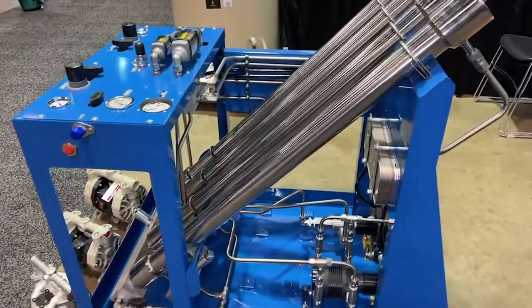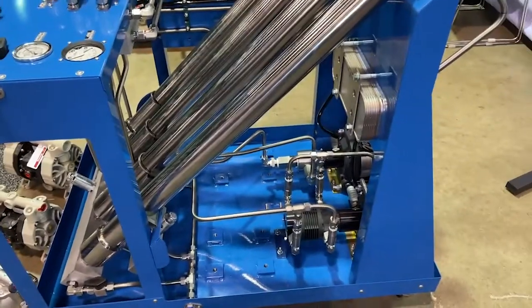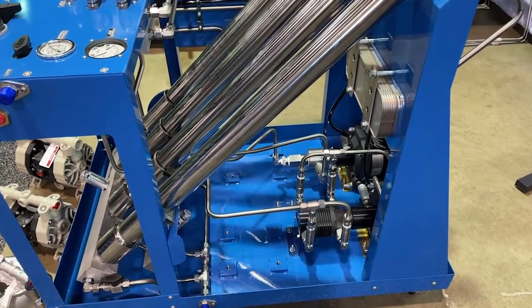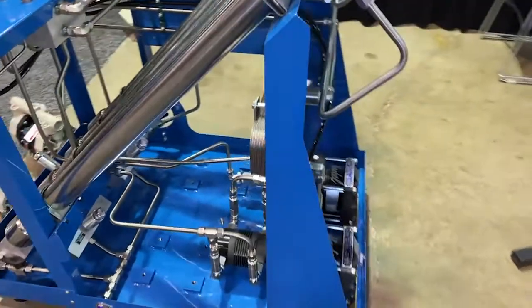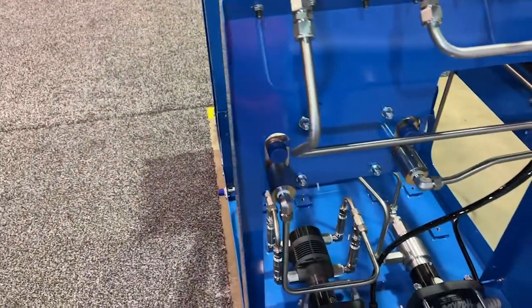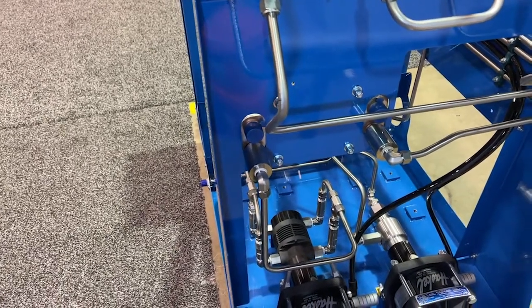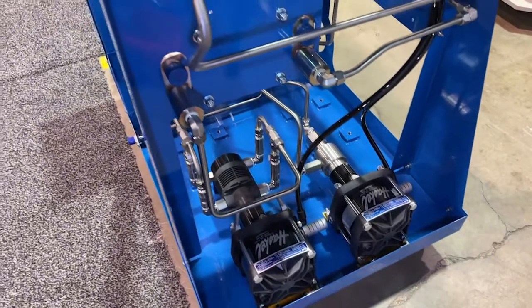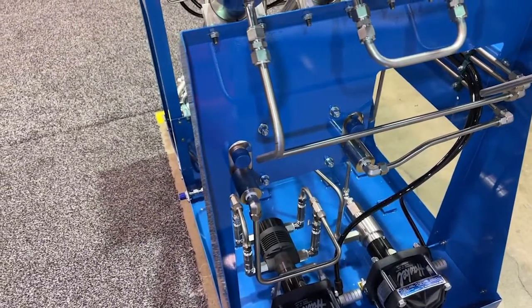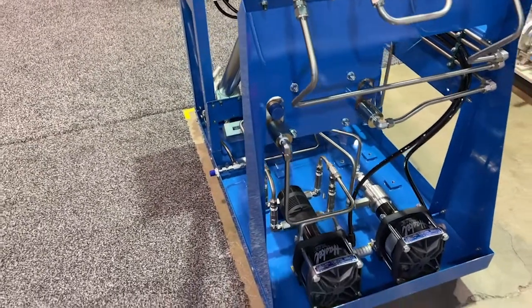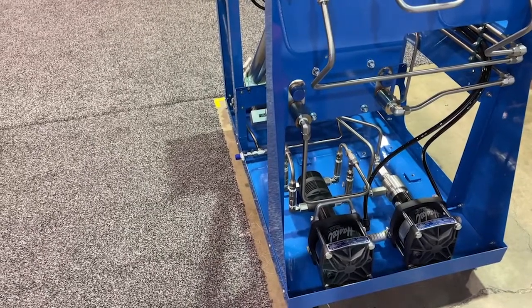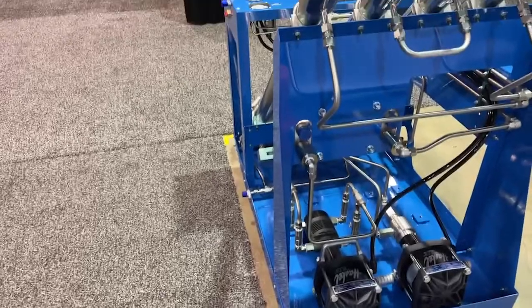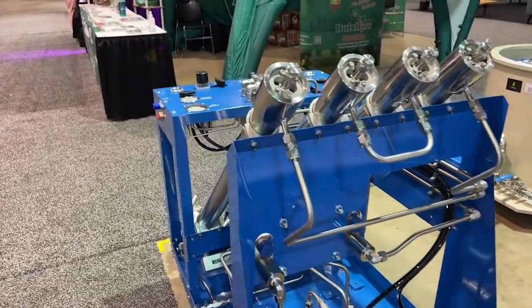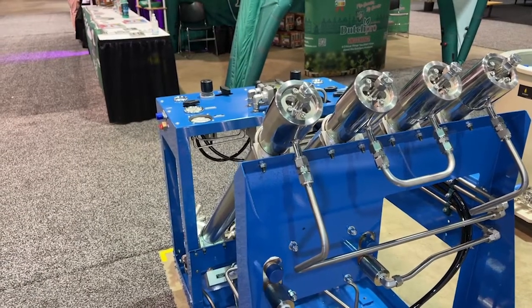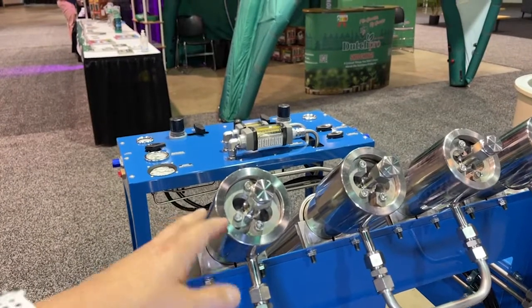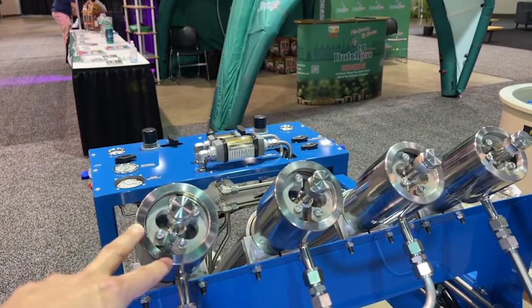But the heat exchanger in this system is primarily used to remove heat from your system, because the pumps generate a certain amount of heat. And so this is an inline heat exchanger that, depending on the application, can be fitted with an external chiller to remove the heat that the pumps are generating. On a small system like this, I believe it's about a kilowatt of cooling capacity that's necessary, so you don't need a big chiller. There may be other instances where you may wish to use a chiller, but in general, it's not needed, especially for solvent recovery. We've actually found that for solvent recovery, warm solutions flow better and recover better than cold solutions.